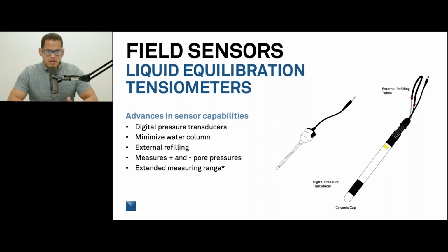One of the biggest advances is the addition of a digital pressure transducer, which allows us to log these sensors automatically. Another big change is minimizing the water column. Traditional tensiometers had long water columns that often ran all the way to the surface, requiring corrections. Now we've minimized that column so we don't need those corrections, and we've added external refilling with things like capillary tubes, so we can still refill from the surface without the big water column.